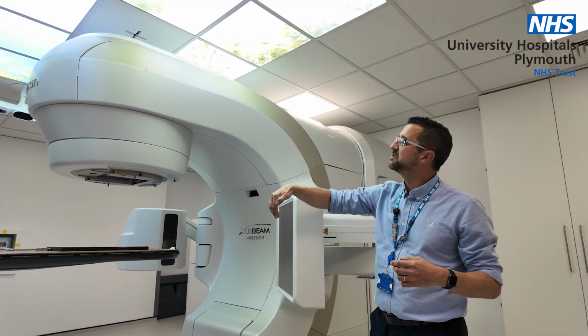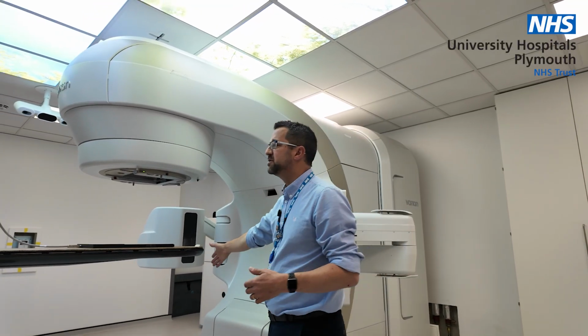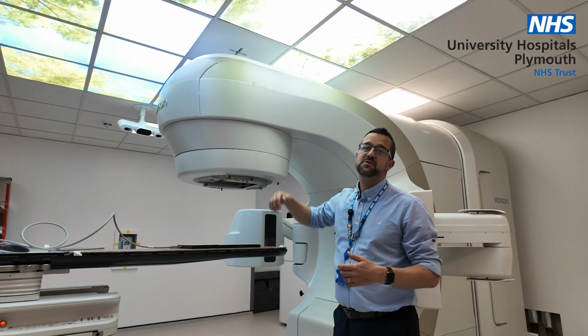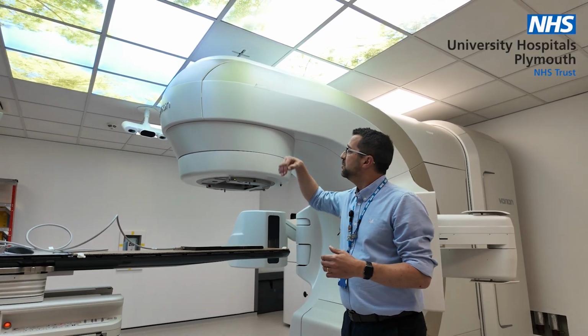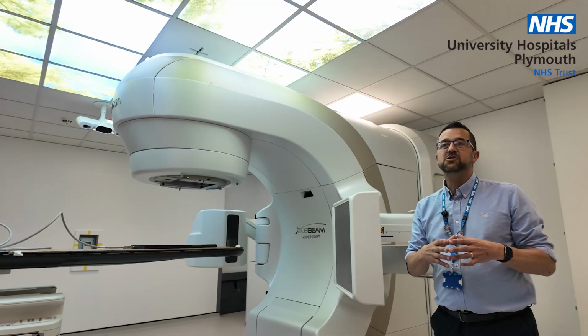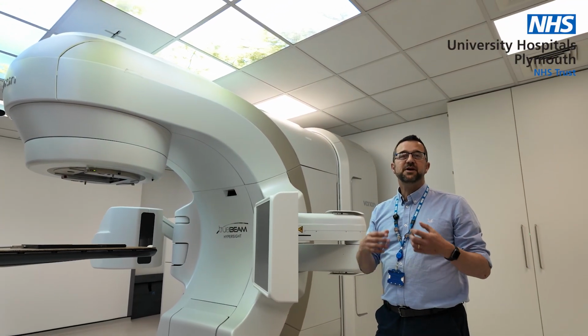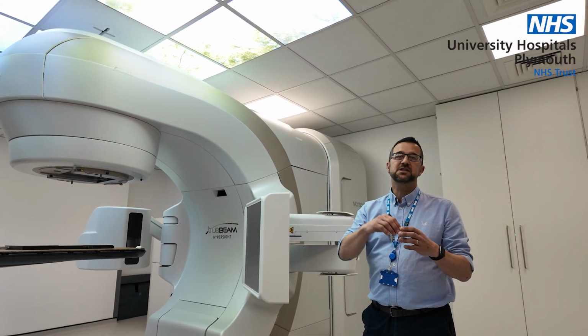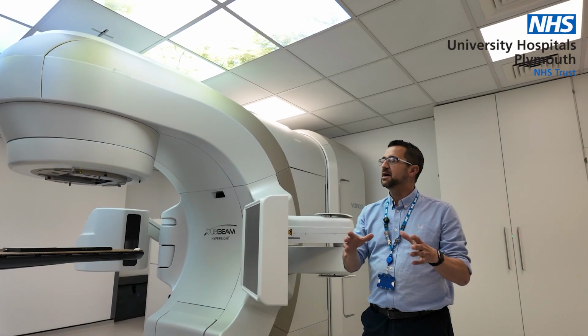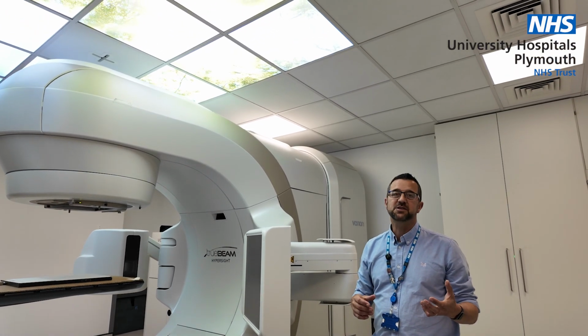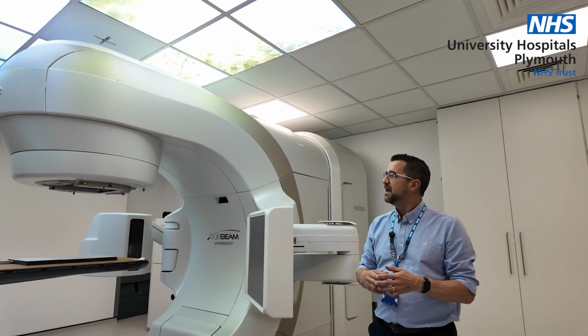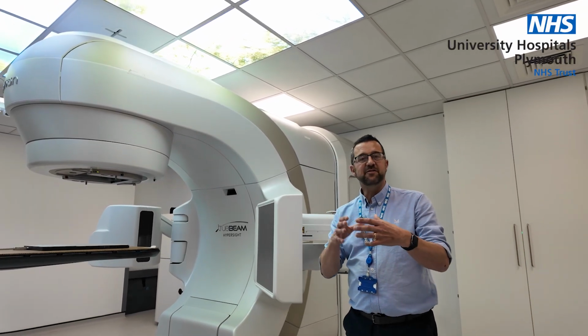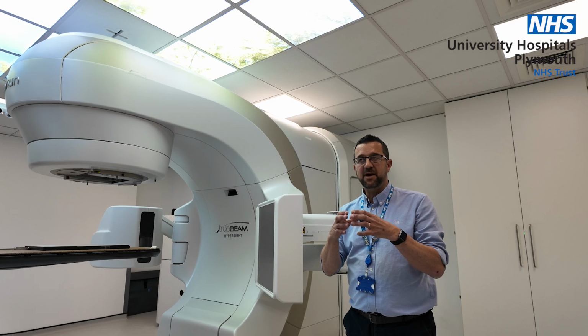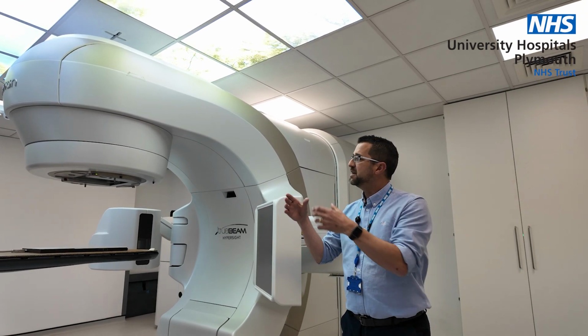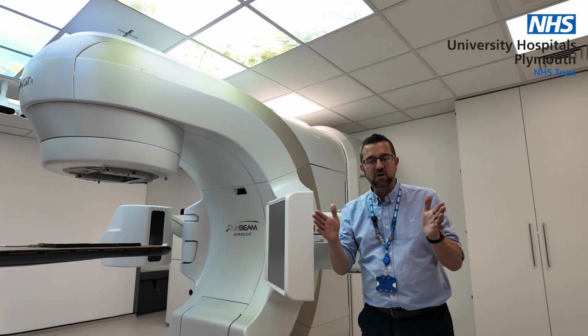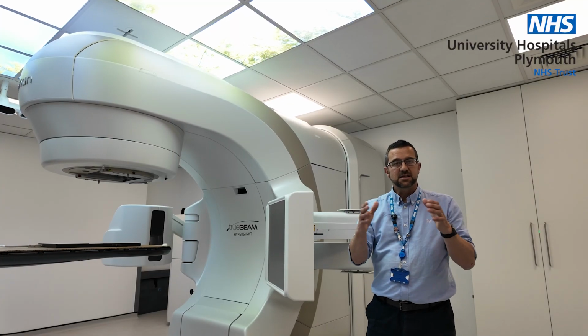We then turn them through 90 degrees because the patients will be positioned on the couch here. And we turn them through 90 degrees with bending magnets. And then most of our patients we treat with photons, high energy X-rays. So we have to create that by driving the electrons into a tungsten target, and that liberates high energy X-rays, which we use to treat the patients. We then shape and focus the photon beam directly through to the patient, and first of all we collimate it to make it a smaller size.